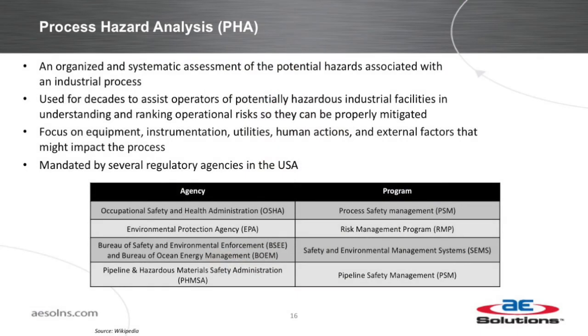The PHA process has been around for decades — it's a very organized, systematic approach to identifying process hazards and understanding the risk associated with them: how likely are they to occur, how bad would they be if they happened. The basic formula for risk is likelihood times consequence. The focus is on equipment, instrumentation, utilities, human actions, and other external factors. For many industries this is regulated — if you fall under OSHA PSM, EPA's RMP program, or some offshore and pipeline sectors, you're required to do some level of process hazard analysis. It's been around for a long time and well accepted by operations groups as part of an ongoing risk management and safety program.